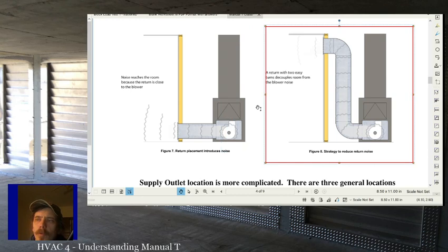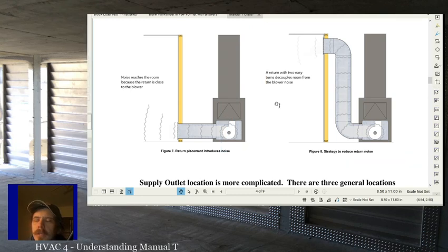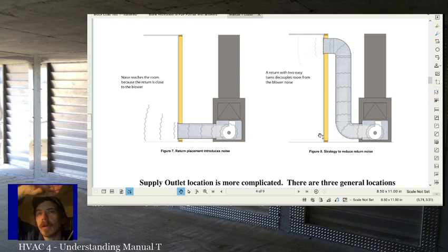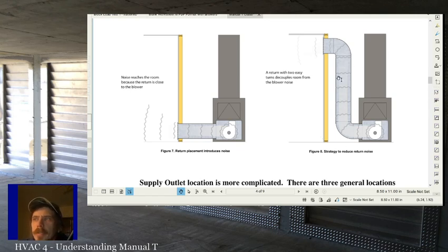It's especially important on rooms where you want privacy, like office spaces and the conference room. You want to have elbows on the transfer, things like that. If you use a transfer grill as a return for a master bedroom or something, you're probably going to want a couple elbows on that. Usually you'll end up going from ceiling to ceiling on the return, so you have to make a 180-degree turn. 180 degrees is a good point to mitigate noise.